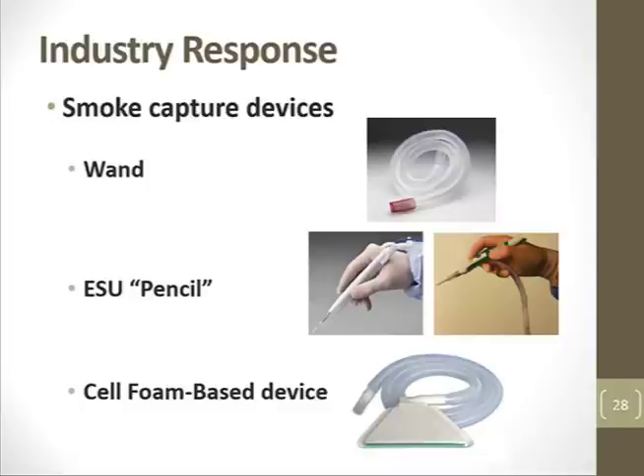The ESU Pencil. This is a monopolar electrode with either an attached or an embedded 3/8 inch tubing attached to it, with the tip of the tubing as close to the tip of the electrode as possible to gain maximum efficiency. Normally this product is attached to a wall suction, which gains up to 5 to 9 cubic feet per minute of airflow, or now it's more commonly being attached to smoke evacuators, which increases its airflow to as much as 15 cubic feet per minute or more. However, if you remember the principles of smoke evacuation, the size of the tubing limits the airflow, and so it is not surprising that smoke capture efficiency may be compromised. And then the cell foam-based device with a much wider surface area for capture.